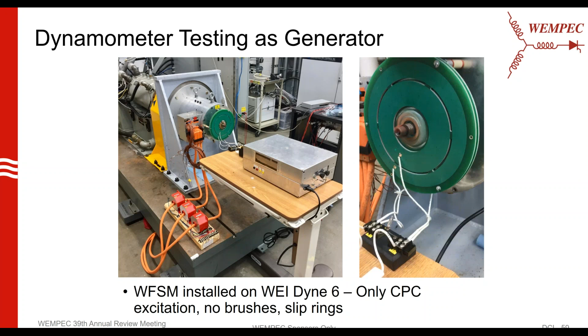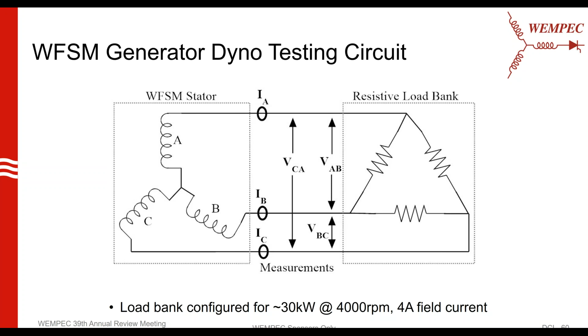So for the testing as a generator, we just connected the machine to a delta resistive load bank, and as you can see here, we were able to achieve line-to-line voltages, and with respect to the CPC current, the RF tank current, we were able to push the machine into saturation and line-to-line voltage, effectively exciting the machine.